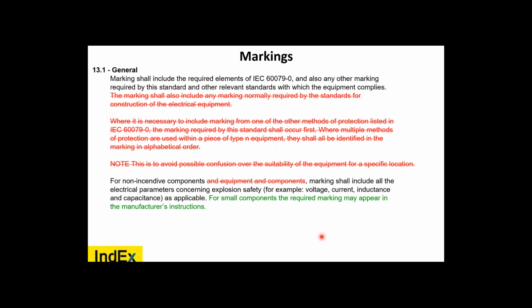You can also find that under 60079-0, 29 markings, point 11, I believe. Very small pieces of equipment do not have to have the EX markings on them. But if a manufacturer does that, that's a very poor way of marking. And you'll find many installers will fail the equipment. So what are we looking at, EXNR for lighting?